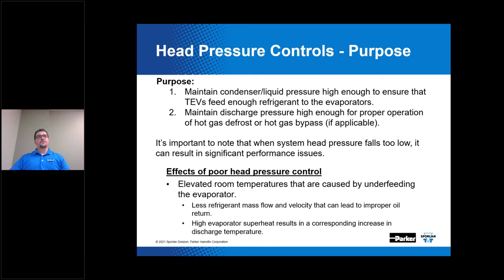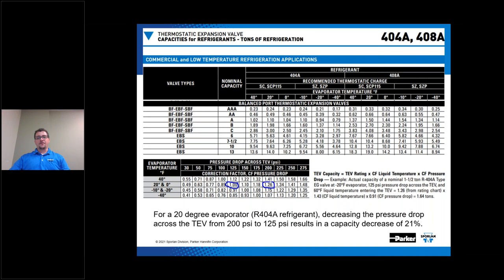If your head pressure falls too low, you'll starve the evaporator of refrigerant, because the capacity of the TEV is directly related to the pressure drop across the TEV. When your head pressure drops, so does the pressure drop across your TEV. Here I'm showing a capacity chart from our Bulletin 1010 showing the capacity of several Sporlan TEVs — thermostatic expansion valves — with R404A refrigerant at various evaporator temperatures.